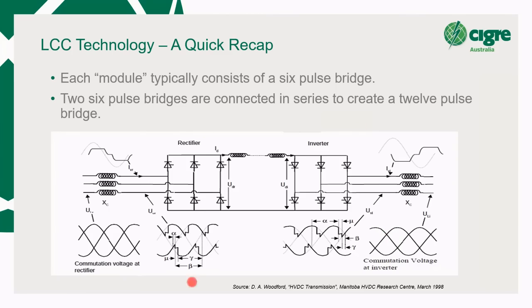The overall conversion process actually requires reactive power to feed it, or it actually draws reactive power. So to minimize the impact on the AC network, you need to feed your converter reactive power. What that means is you need a number of filters both to handle the harmonics, but also to feed the reactive power requirements of the converter.